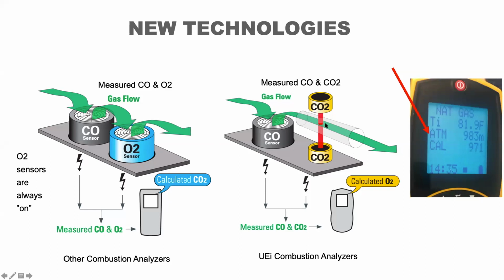So this is like a very sophisticated type of lab bench measurement. In fact, organizations that measure really high-end equipment use non-dispersive infrared analyzers. And this is a miniaturized version that you have in your hand when you have these UEi analyzers. So it measures the absorption of infrared energy in the range of the CO2 sensor, and that sensor detects the difference in light, which will then give you a CO2 level.